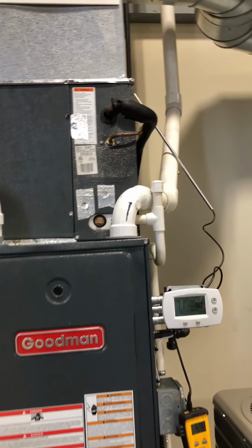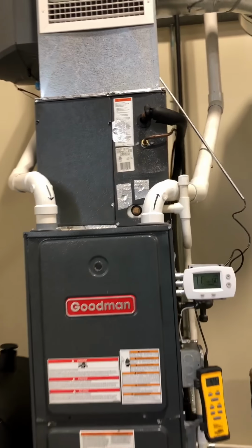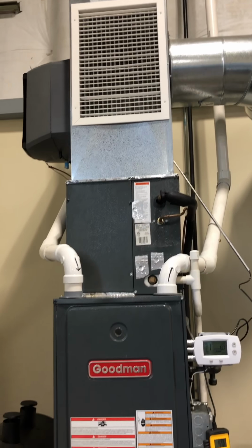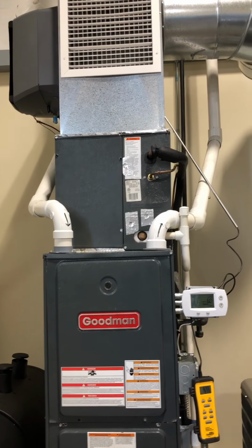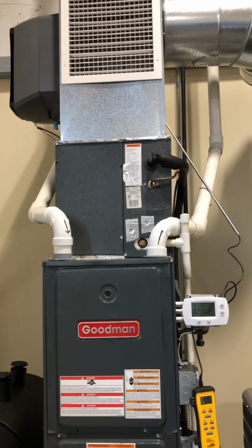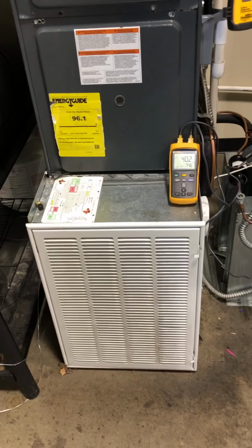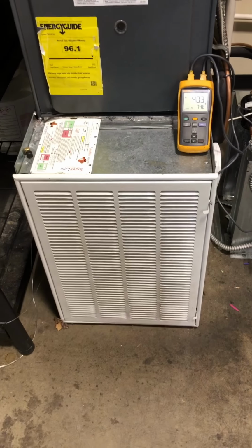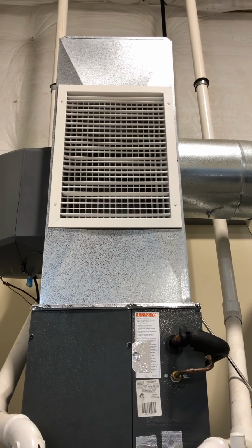So if I have a 20 degree split at the evaporator, and I go into the house and I take it at the return and a supply vent, and I only have 15, that means I'm losing 5 degrees somewhere. There's probably a problem with the ductwork. That's why I like to check it in the house. Just another thing I can eliminate of being a problem. Okay? But we want to take in the return air, the temperature we have going in, and the temperature we have coming out. We want to see about 20 degrees difference.